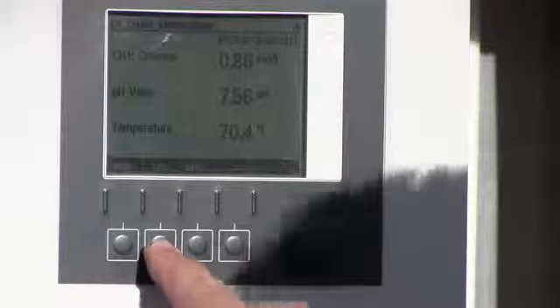When you walk up to the unit, you've taken your DPD sample, and now you want to do a calibration for the chlorine sensor. You hit this button for cal. Nothing happened because the backlight came on. I hit it again. Screen changes. We have the option here, highlighted at the top, to calibrate the chlorine sensor. I use the jog shuttle button at this time and push it in.